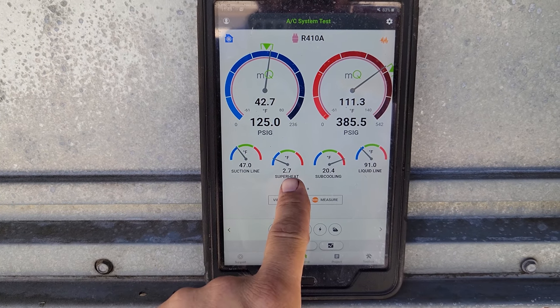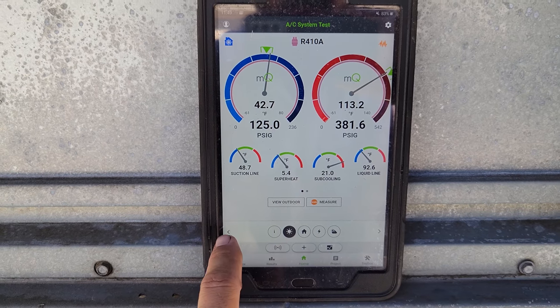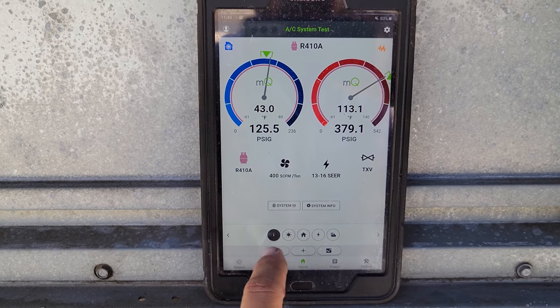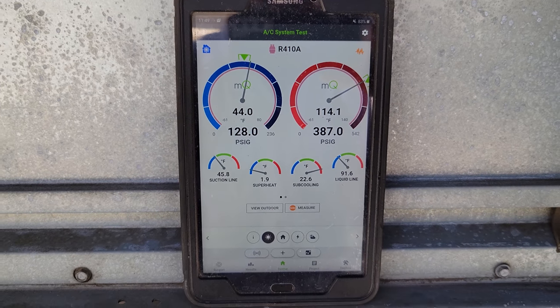This is the first stage. The superheat is throttling as the valve's kind of adjusting. The system's still stabilizing out. Subcooling's about 20 degrees. Pressures are looking a lot better on the first stage now that we've added a little